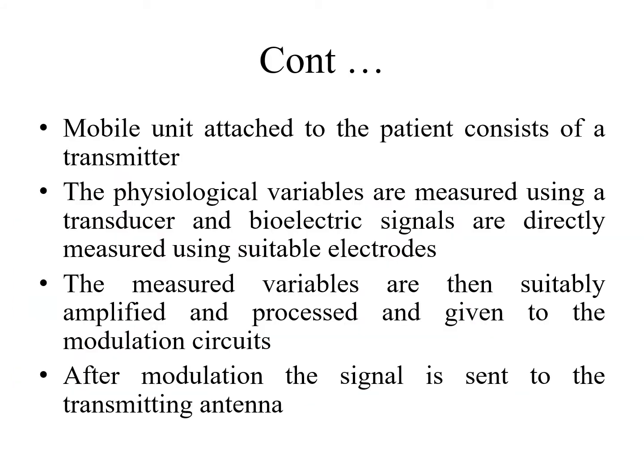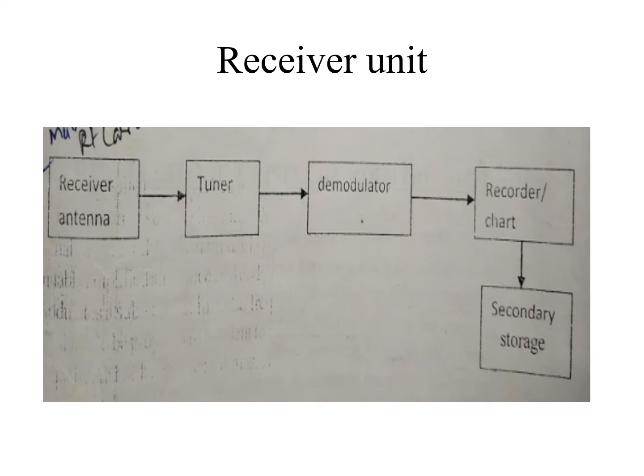The mobile unit attached to the patient consists of a transmitter. The physiological variables are measured using a transducer, and bioelectric signals are directly measured using suitable electrodes. The measured variables are then suitably amplified and processed, and given to the modulation circuits. After modulation, the signal is sent to the transmitting antenna.